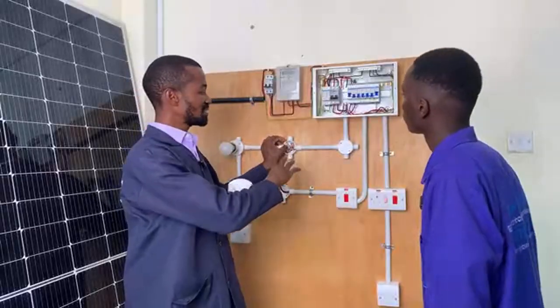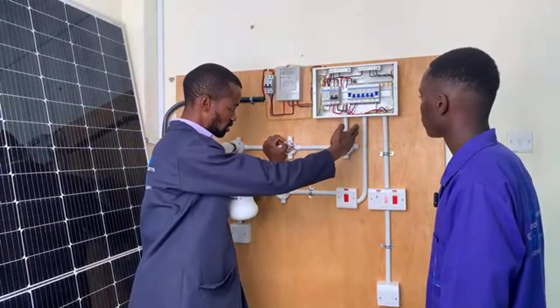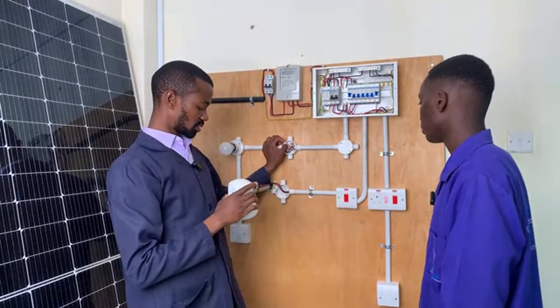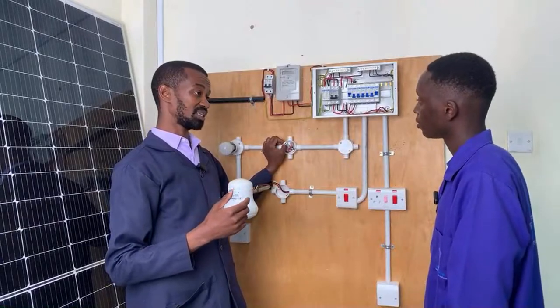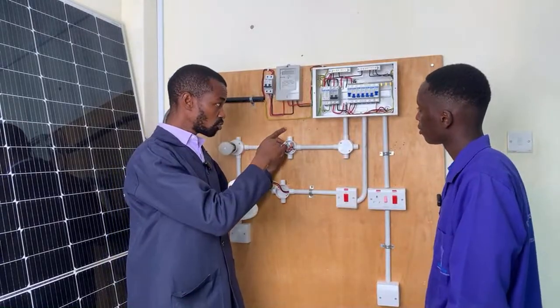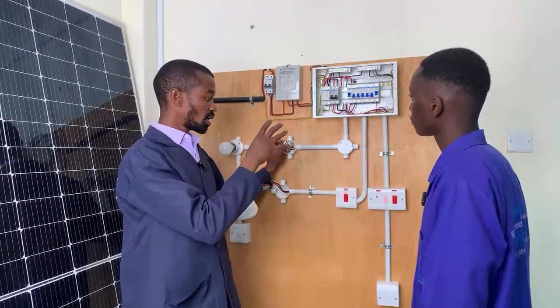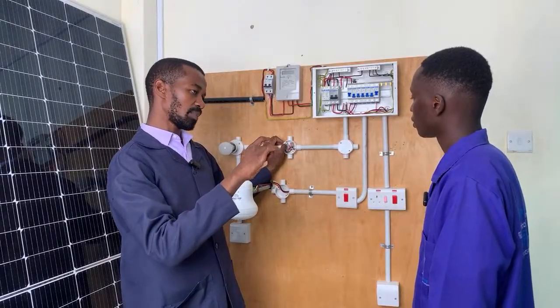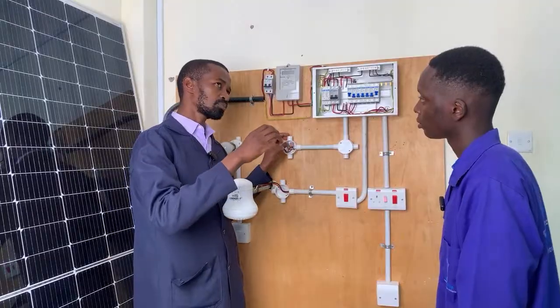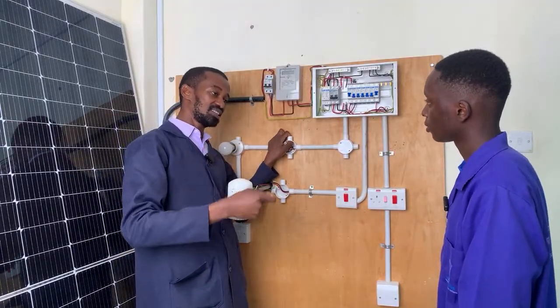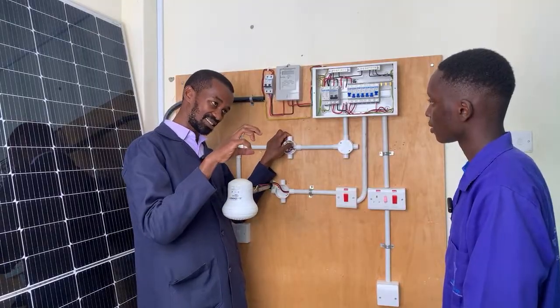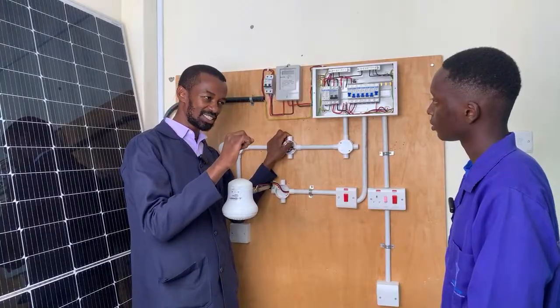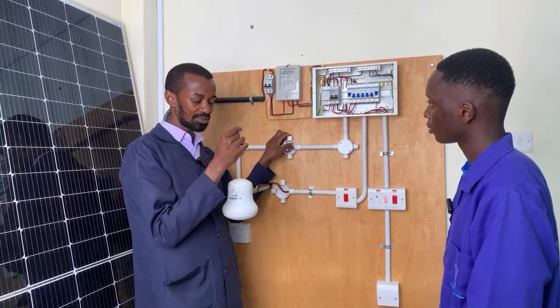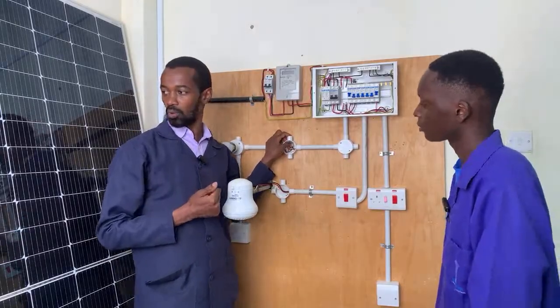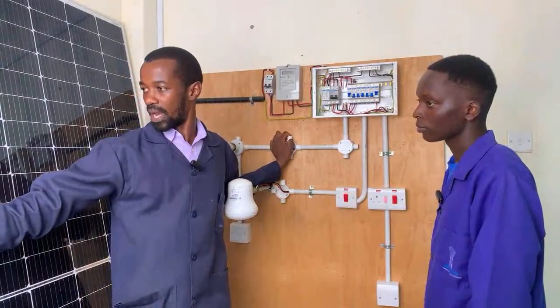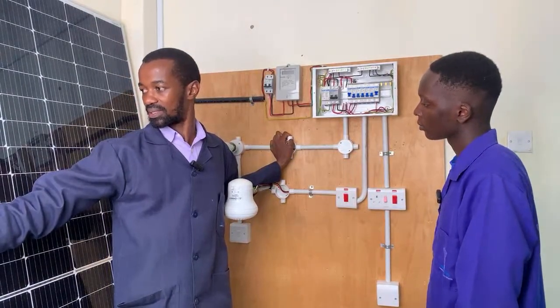Now, assuming this is a long circuit from the consumer unit to the switch and all the way to the shower head, you'll find it's a very long distance, especially in a typical house connection. If you use a 2.5 over that long distance, there will be an issue. Remember from high school, the resistance of a wire increases with distance and length, as well as with the size of the wire. If the wire is too small, the resistance will be higher, so we need to be cautious. For me, I would go with 4.0 as the minimum.